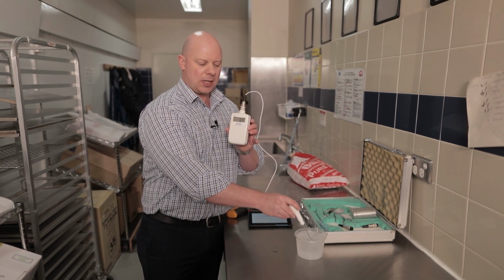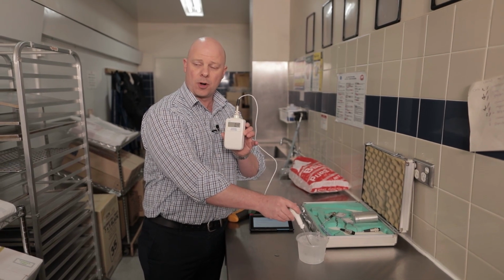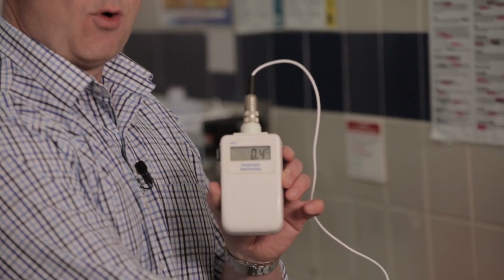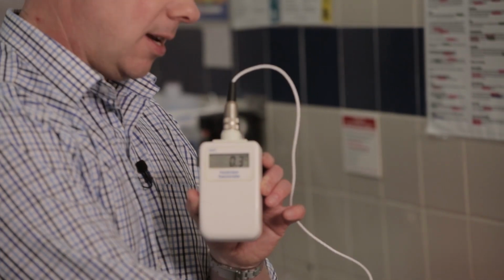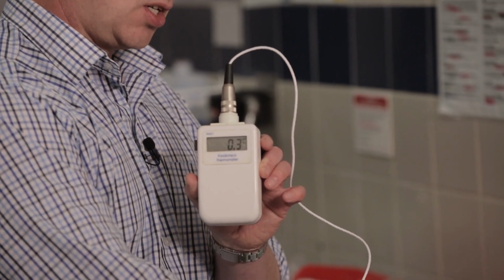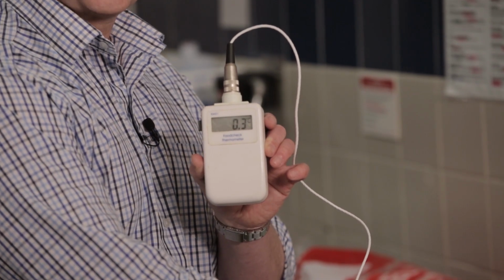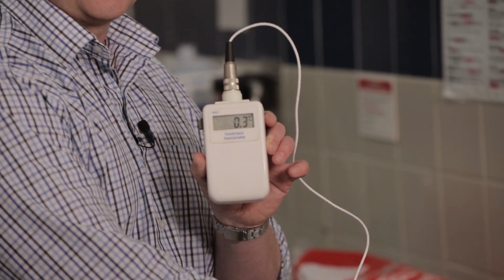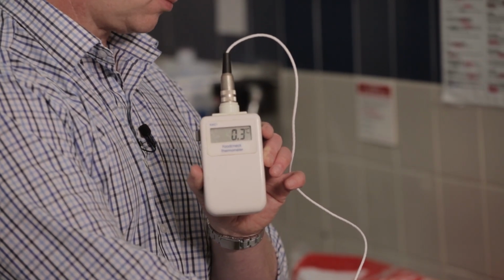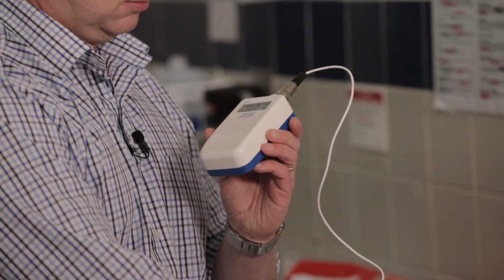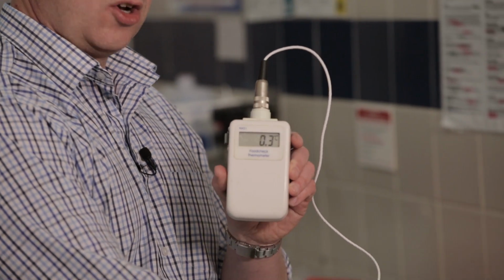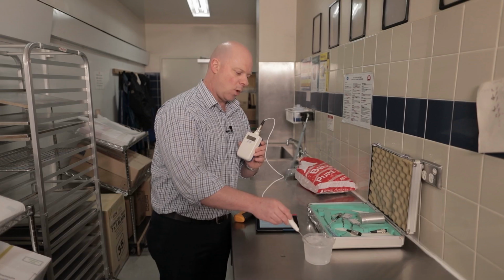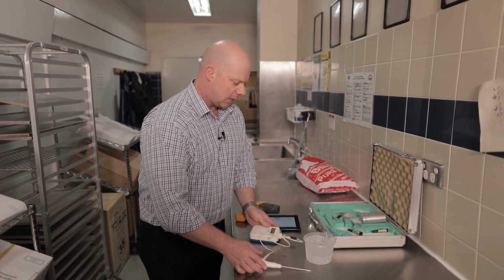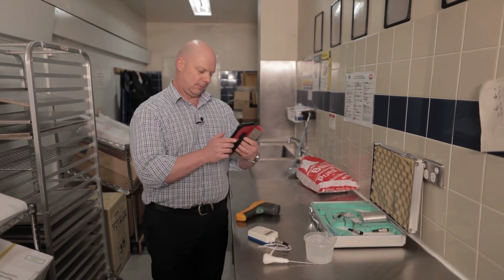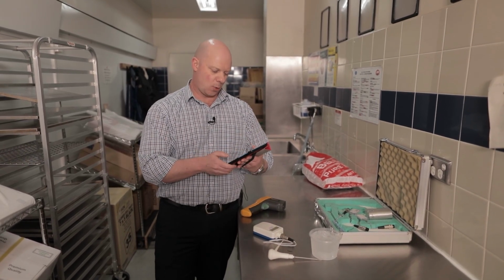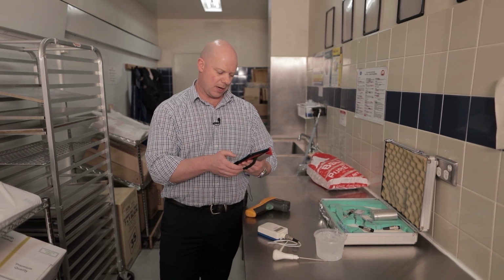If we look at the temperature on the digital thermometer at the moment, it's saying 0.4 degrees. So we're happy that this thermometer is accurate within plus or minus 1 degree, which is the food standards code requirement, and we can move on. It's actually gone down to 0.3 degrees. Once you've done that, grab your tablet and under ice point test, put 0.3 degrees.